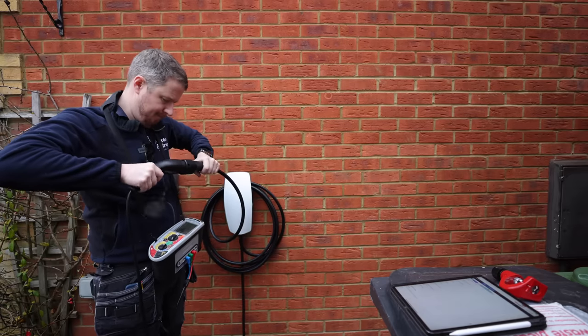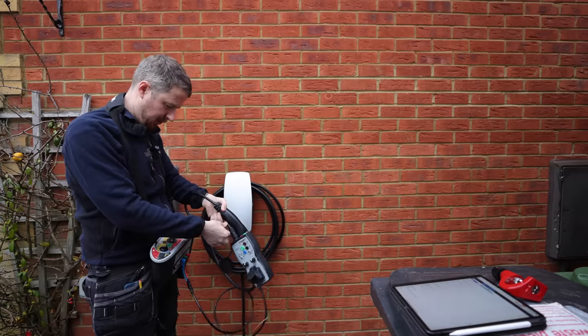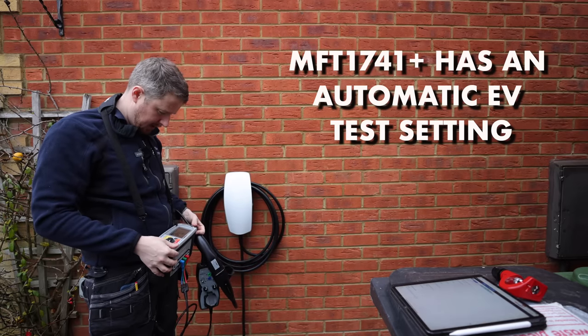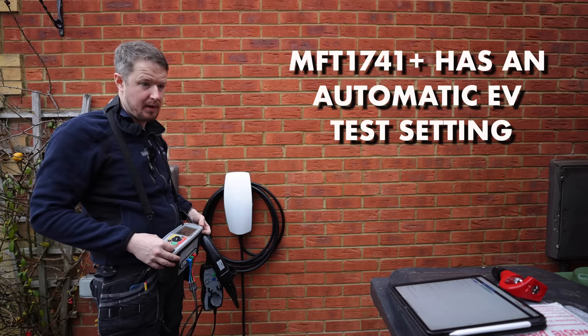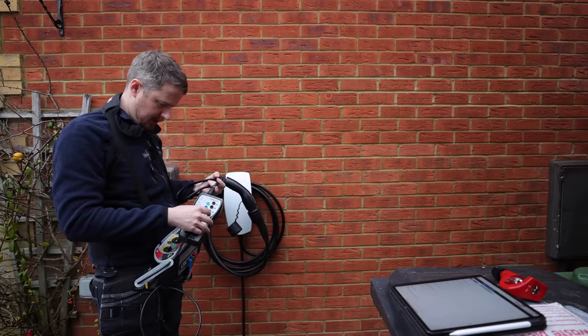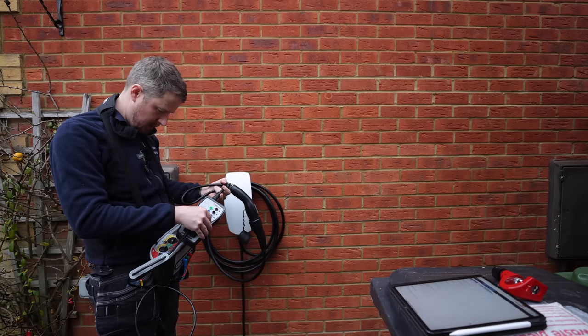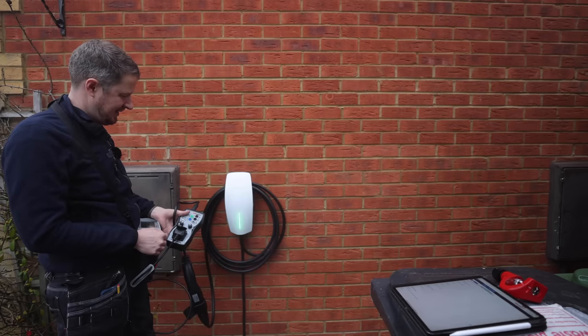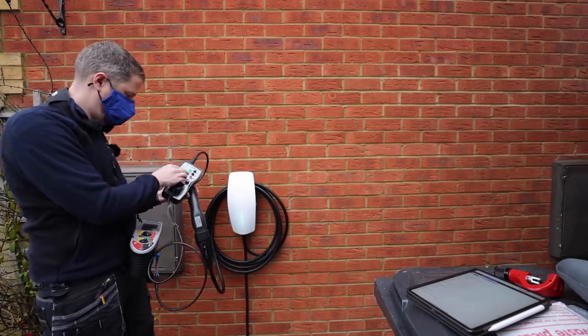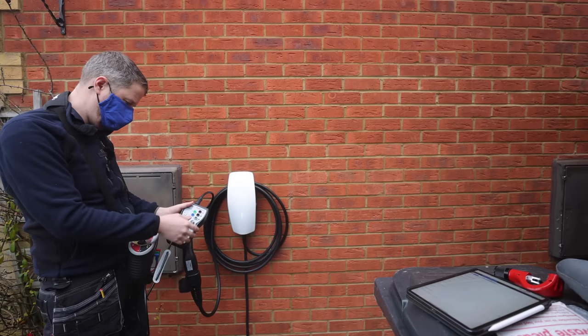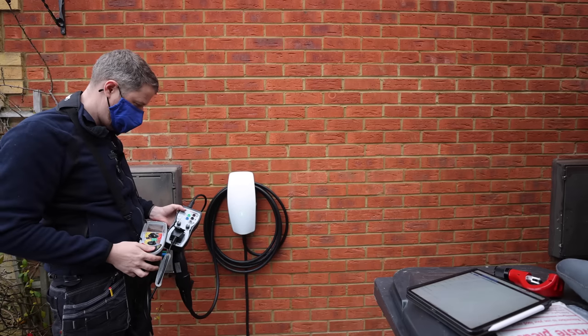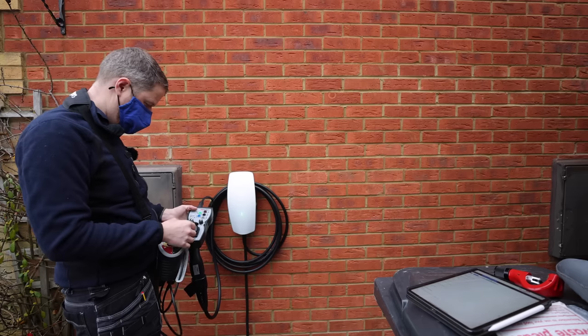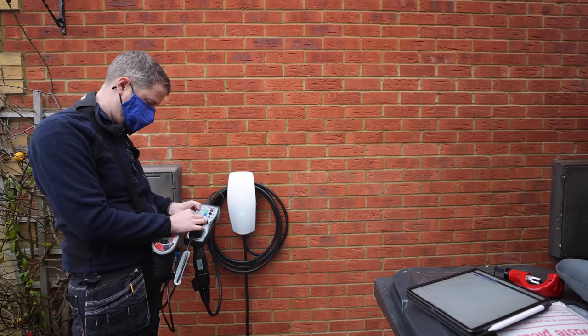So what we're going to do now is do our functional and our Zs, and we've got this amazing Megger EVSE adapter that goes with the Megger MFT1741+. And I've never, I've not used this yet before to test EV charging points, so it's going to be interesting to see if it does what it's supposed to do, which is to not trip the internal RCDs and stuff, and you actually can get the charger to turn on. So to do that, put it on C. There we go, Tesla charger is all livened up now.